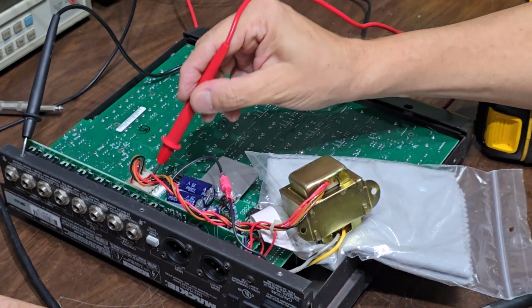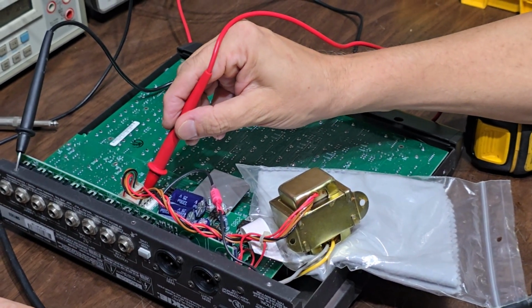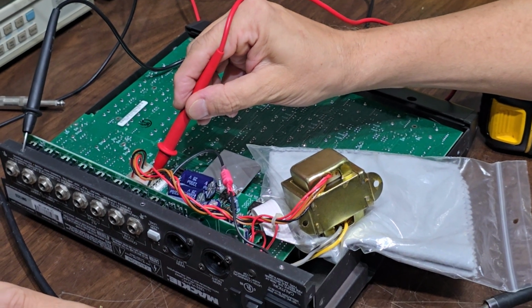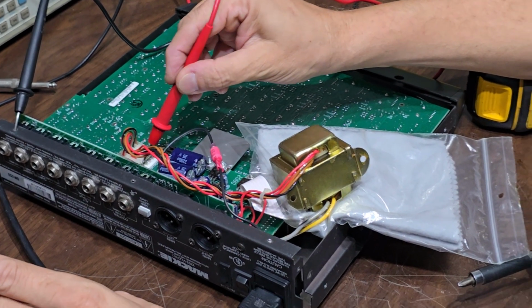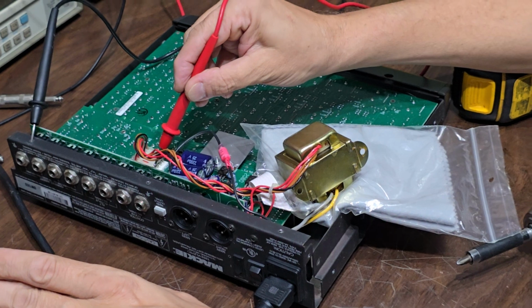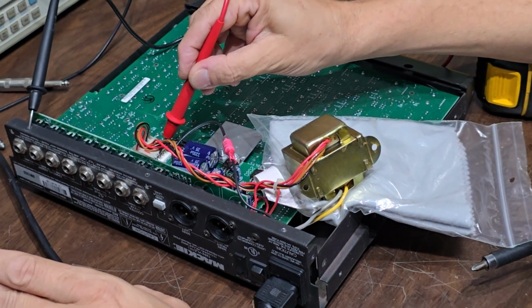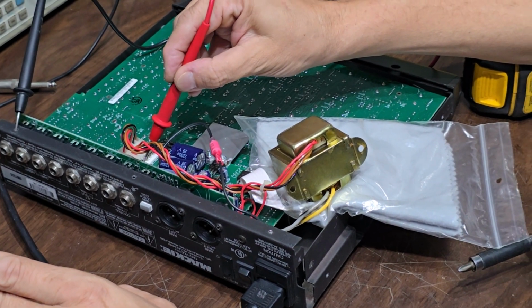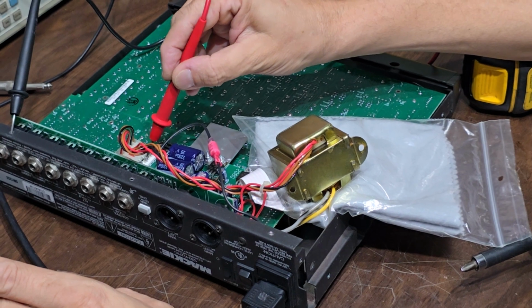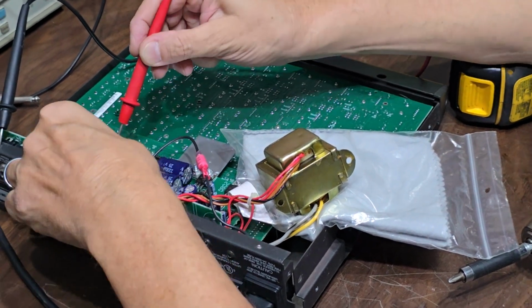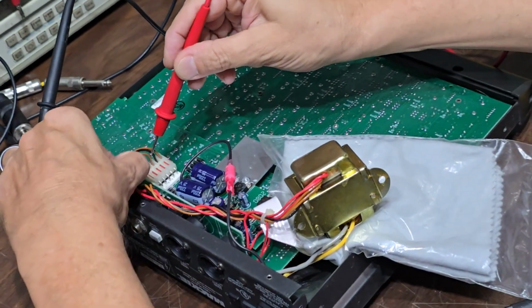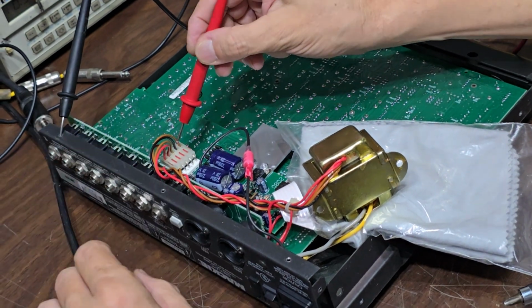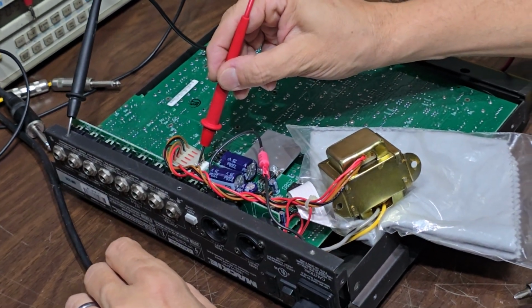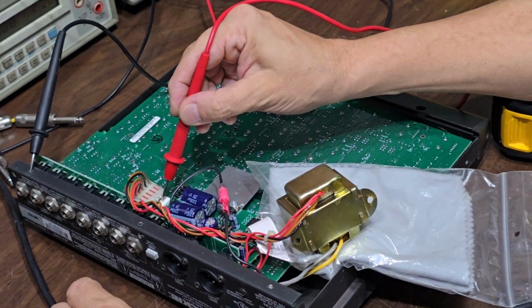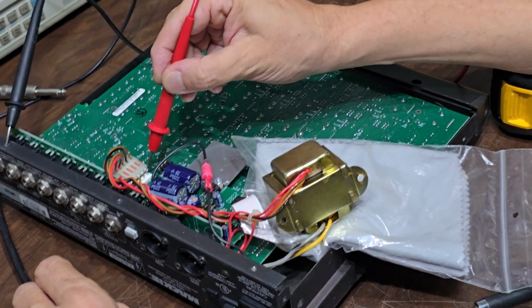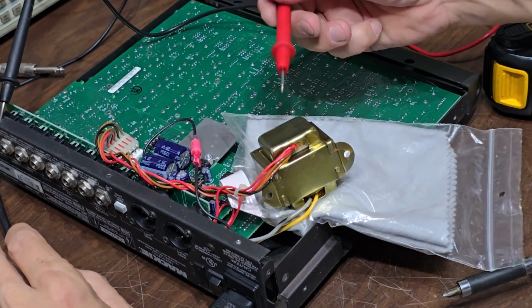You'll have AC on this side, so: 105 millivolts AC reference to ground, 112 millivolts AC reference to ground, and 0 here, so this is actually ground, you can see the stripe. Actually that's brown, so brown-black-brown is probably its own secondary. So ground, nothing, nothing. We're not getting anything coming out of just the power transformer.